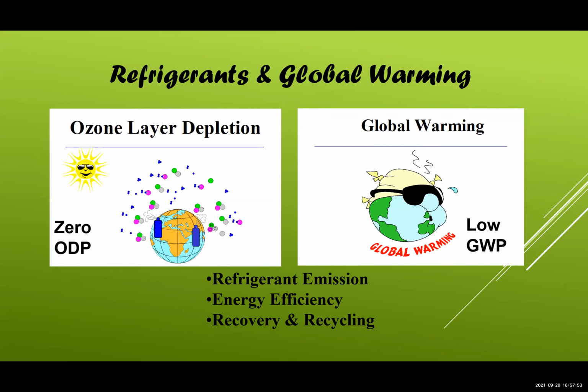So if you want to take both into consideration, we need to worry about refrigerant emissions throughout its life cycle, energy efficiency, because energy efficiency is responsible for CO2 release from power stations. So the more the energy you put in, the more CO2 you release. So energy efficiency becomes an important issue. Recovery and recycling. Already Yash had said, how do you manage refrigerants by recovering and recycling?